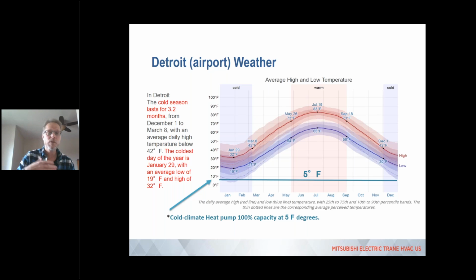On average, over the last number of years, the average temperature is only around 19 degrees in the Metro Detroit area. Our systems can do 100% heating capability at 5 degrees, and they can do somewhere around 76% capacity on average. Some are a little higher, some are slightly lower. But as you can see, we could do a very good job utilizing this cold climate heat pump for your heating sources in Michigan.